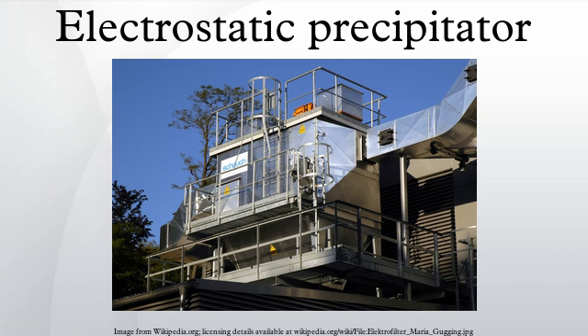In high resistivity dust layers, the dust is not sufficiently conductive, so electrical charges have difficulty moving through the dust layer. Consequently, electrical charges accumulate on and beneath the dust layer surface, creating a strong electric field. Voltages can be greater than 10,000 volts. Dust particles with high resistivities are held too strongly to the plate, making them difficult to remove and causing rapping problems. In low resistivity dust layers, the corona current is readily passed to the grounded collection electrode. Therefore, a relatively weak electric field, of several thousand volts, is maintained across the dust layer. Collected dust particles with low resistivity do not adhere strongly enough to the collection plate. They are easily dislodged and become re-entrained in the gas stream.